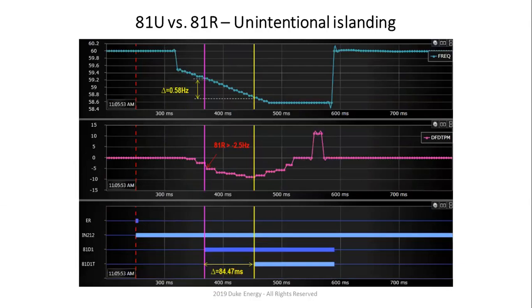That's essentially when we would actually go to the islanding mode, right? But if you take a look at the middle one, you can see that 81R, rate of change of frequency, reaches minus 2.5 hertz. And 2.5 hertz is something that I have found in literature that everybody's talking about as a setting. So I just wanted to use something as a frame of reference for this stuff.